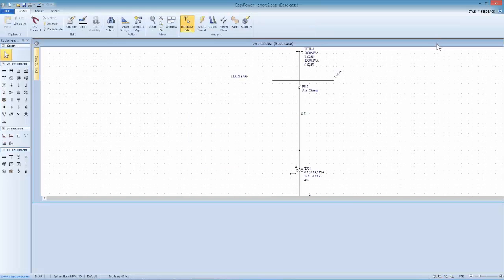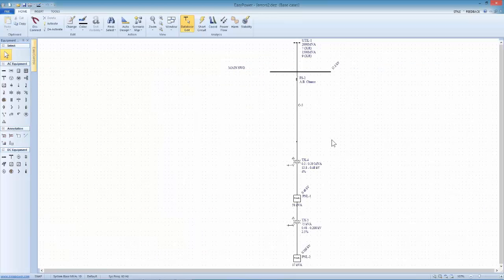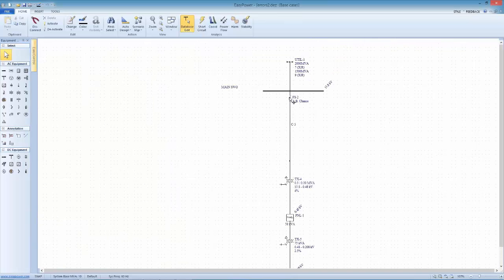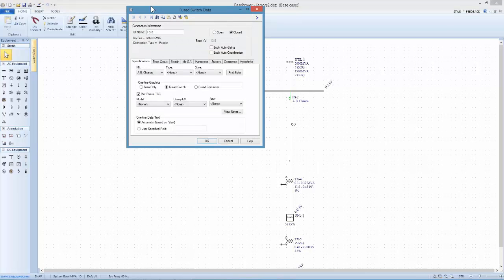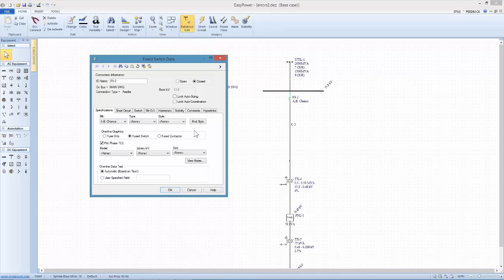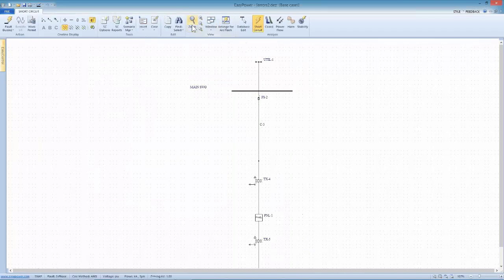As I go back to the database editor, I'm not going to change anything just yet. I tell myself, well, I got a fuse here, why isn't that working? Even if I don't have a fuse, what I recommend is starting by putting a fuse in the system and making sure it's fleshed out. In this case, I generally use an AB Chance because it's medium voltage, a fuse link, Model T, 10 amps. What that allows me to do is go in, short circuit focus, fault the buses.